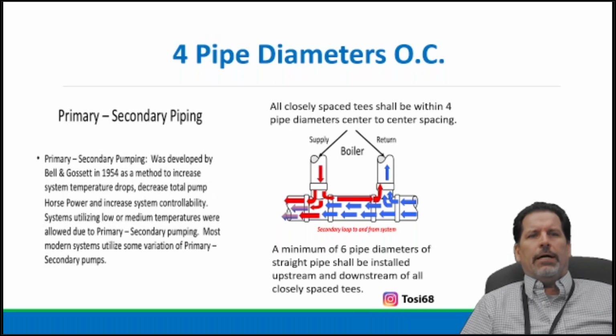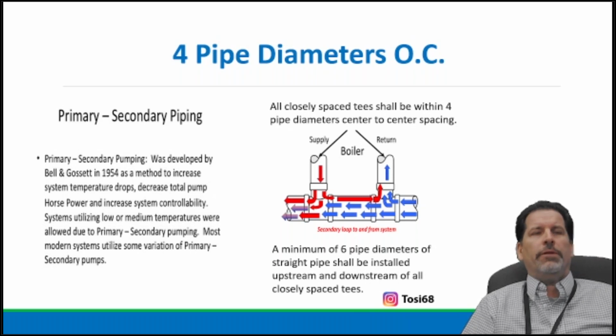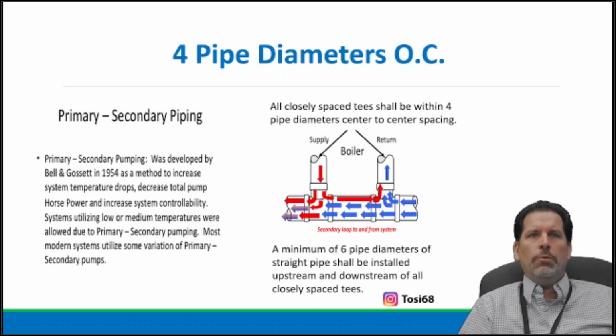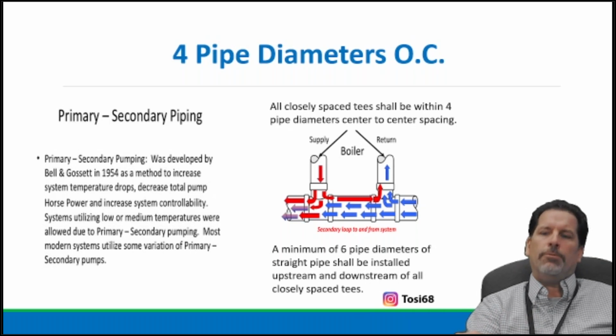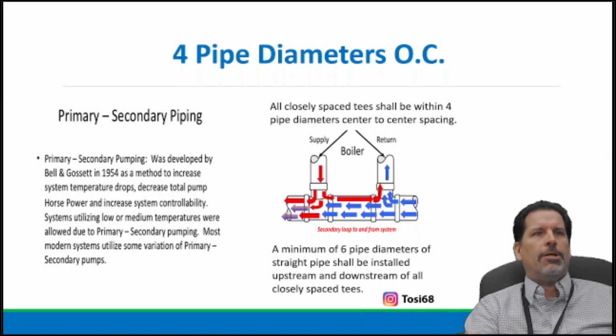The idea is allowing the boiler to have its own performance, meaning flow rate, versus what the system performance or flow rate requirements are, whether zoned or one large loop around a warehouse. It holds true for closely spaced tees too, you can build it or buy it, just know what on-centers are: no more than 4 pipe diameters on center, and entering and leaving pipe should be roughly 6 pipe diameters before and after.